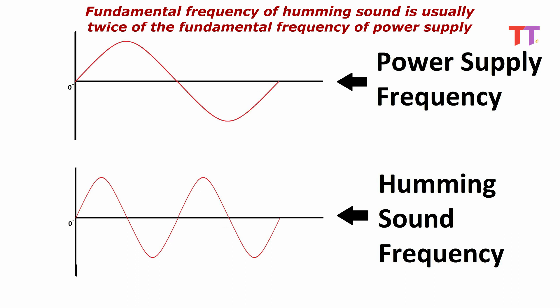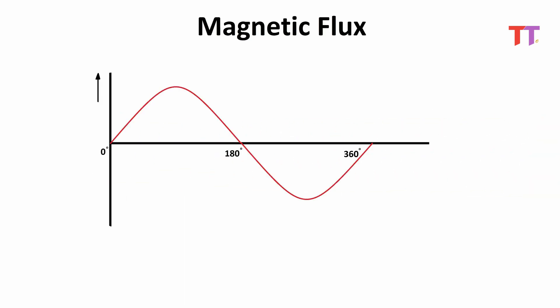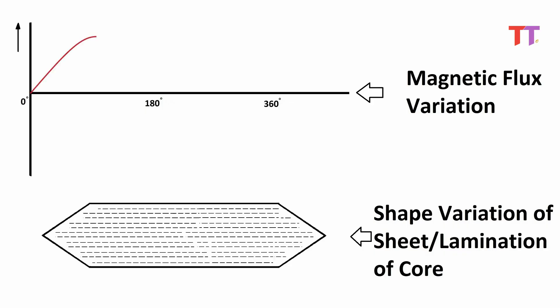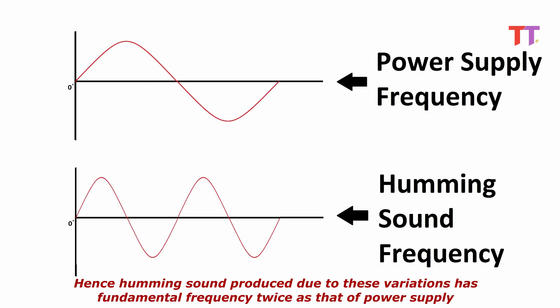The fundamental frequency of the humming sound is usually twice the fundamental frequency of the power supply. For example, the humming sound frequency would be 120 Hz for a 60 Hz power supply and 100 Hz for a 50 Hz power supply. As we know, the magnetic flux produced in the core has sinusoidal behavior similar to that of current and voltage. In the waveform, flux reaches its peak twice in one cycle — once on the positive side and once on the negative side. Hence, the transformer core extends and retracts itself twice in one cycle of magnetic flux, and the humming sound produced has a fundamental frequency twice that of the power supply.